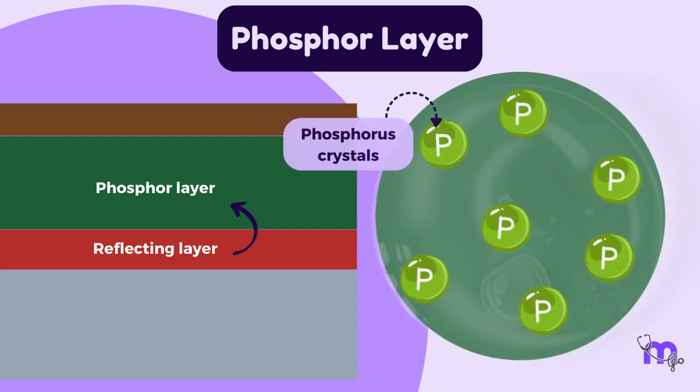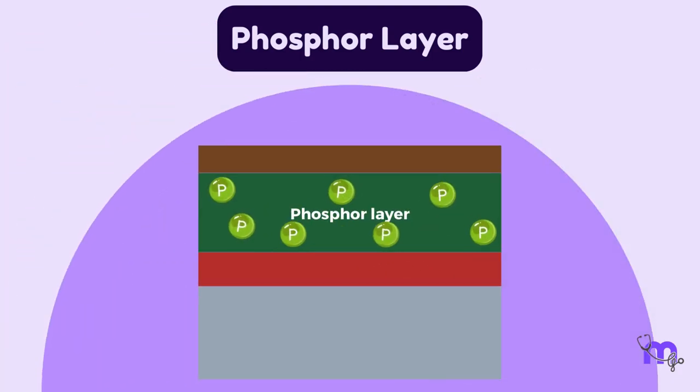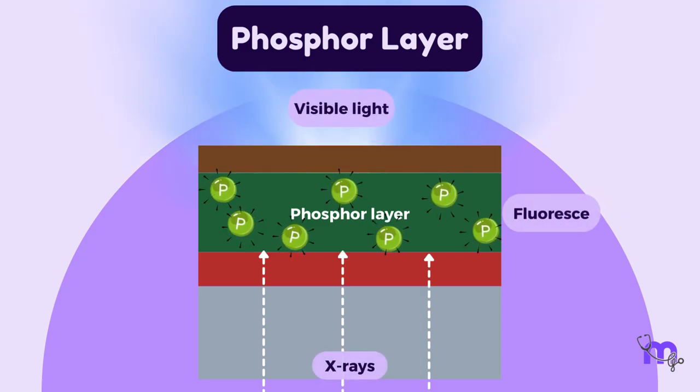The third layer is the phosphor layer, placed over the reflecting layer. It contains phosphorous crystals suspended in a polymeric binder. This is the most essential layer, as the phosphor crystals absorb the X-ray photons, fluoresce, and emit visible light.